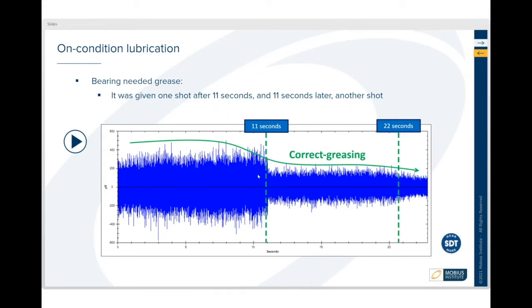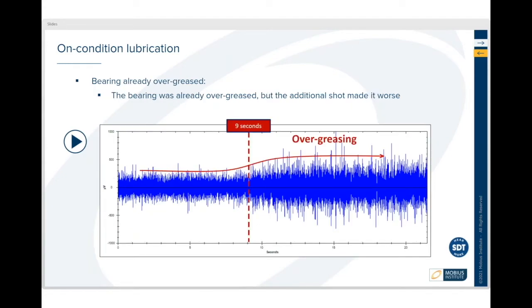Here you can see grease was injected. There was already grease in there and that's the sound level. The sound dropped down when the grease reached, and so that looks good. But if you keep greasing then the sound level might rise up and now you've over-greased it. You could physically damage the bearing and the seals. The grease might go into the electrical windings. It can cause the bearing to overheat and other problems, so we need the right volume of grease.